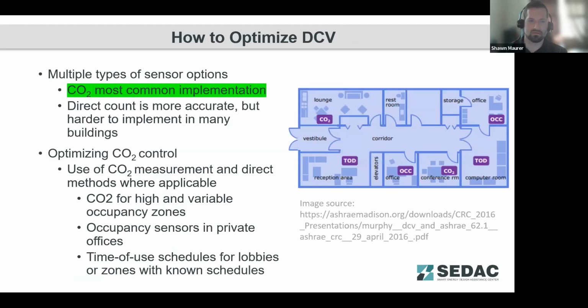And so what we're touching on here, multiple types of sensor options exist. CO2 is the most common implementation. A direct count of building occupants is going to be more accurate, but it's harder to implement in most buildings. We have seen for some stadium type structures or auditorium type structures where they can have door counter sensors that count occupants going in and out of the building and adjust ventilation that way. But for CO2 control, typically you're going to see those in spaces that have variable time of use, but relatively consistent occupancy levels. So making sure that CO2 measurement is applicable to the space.